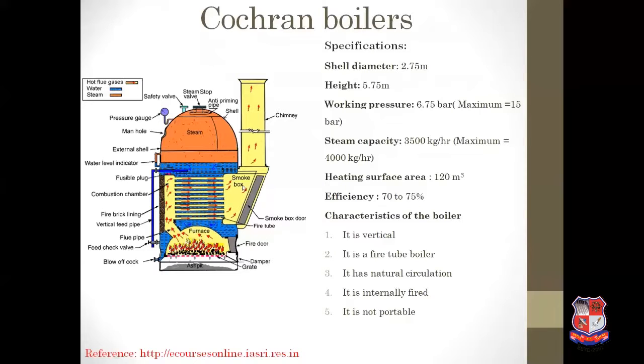The Cochran boiler consists of a vertical cylindrical shell. At the bottom of this cylindrical shell, a firebox is provided. Inside this firebox, a grate is provided, and below this grate there is an ash pit. On the upper side of this grate, coal is supplied by opening the fire door. At the top of the firebox, a short flue pipe is provided, so hot gases passing through this flue pipe experience a considerable increase in velocity.